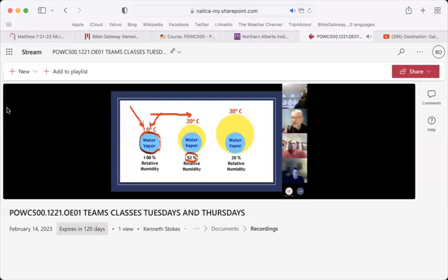In this volume of air, we still have the same amount of water, whatever that amount is. But if we double the temperature, we increase the volume of the air, so there's less water, which means there's a lower relative humidity. So if we bring that same air into the building from 10 degrees outside and we continue to heat it, when we get up to 30 degrees C, probably you wouldn't go that high in your building, but our relative humidity is going to drop. It's going to drop some more. The same amount of water vapor is in that air, but the volume of that air is greater, so we end up with less relative humidity.